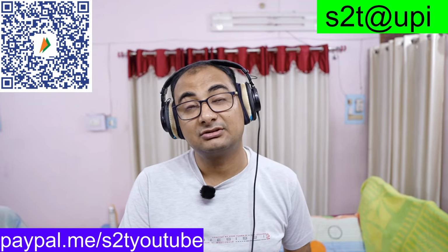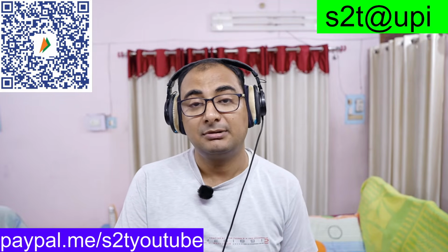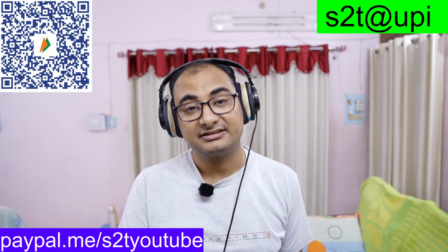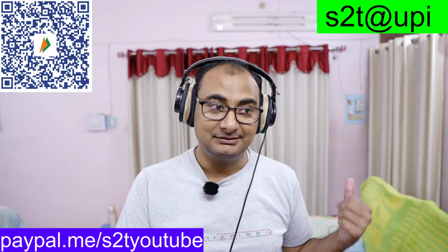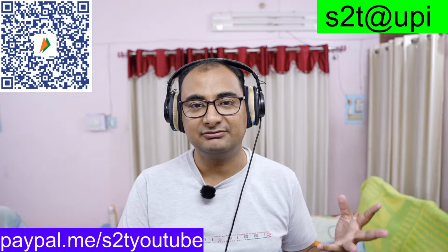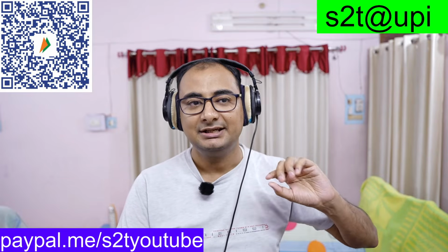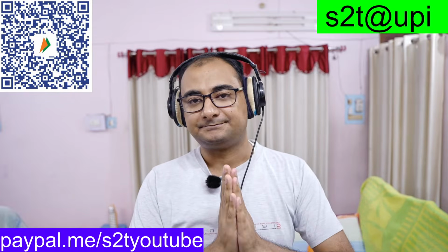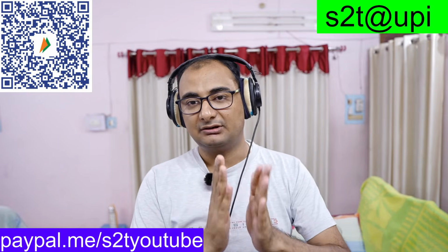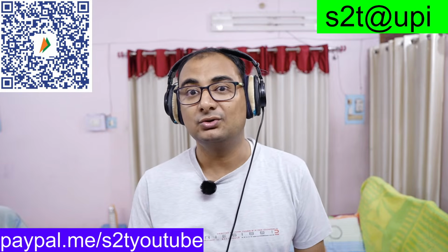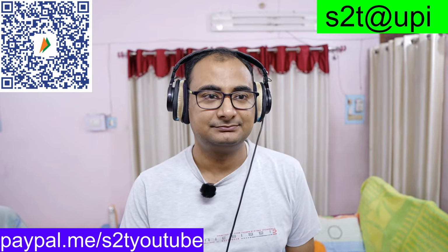Oh, that's another aspect of the reluctance motor. It has horrendous power factor. And before you say, oh, what if you do a power factor correction circuit, that circuit still has to deal with it. The brushless AC synchronous motor is one of the few where you can originally have it such a way, because you control basically the rotor current. You can make sure that it will always remain at a power factor of 1. You don't fix it, it does not go to bad power factor.